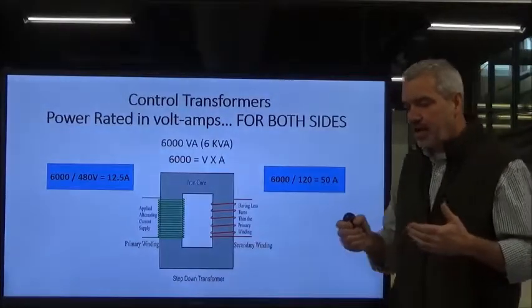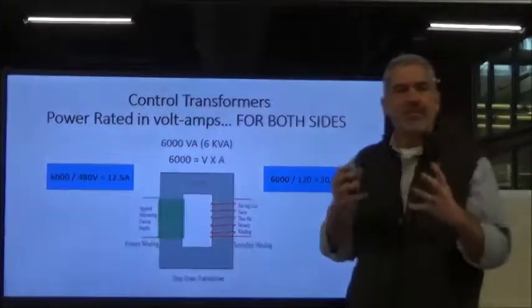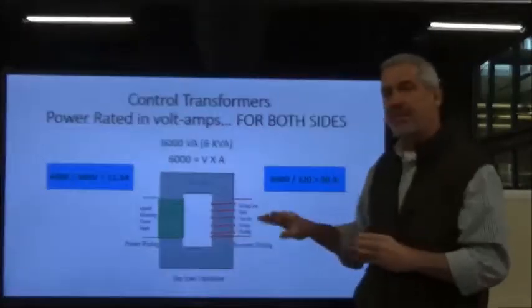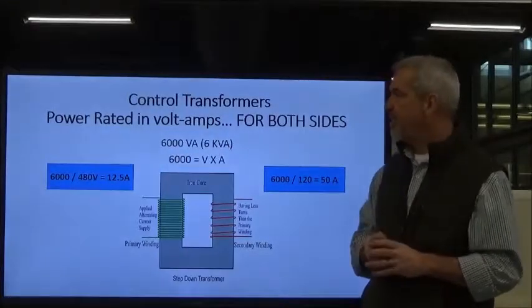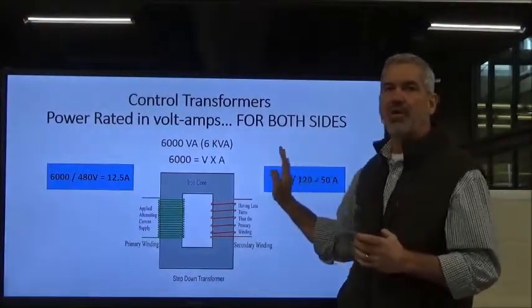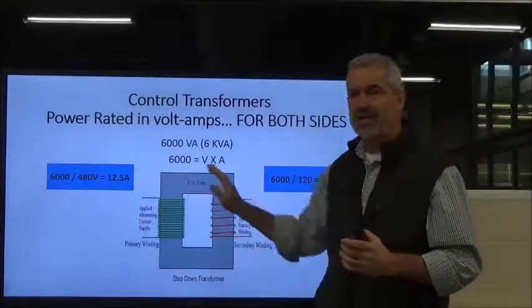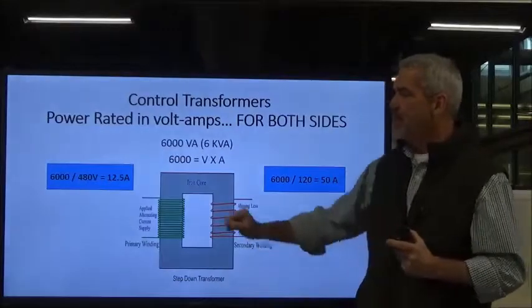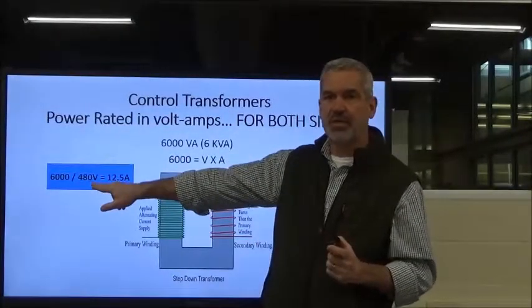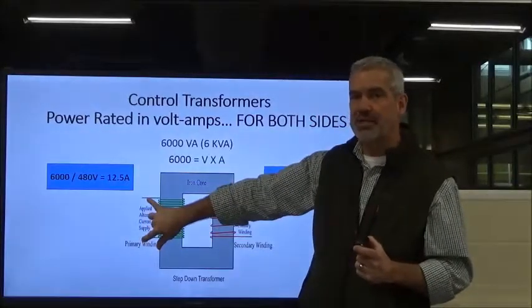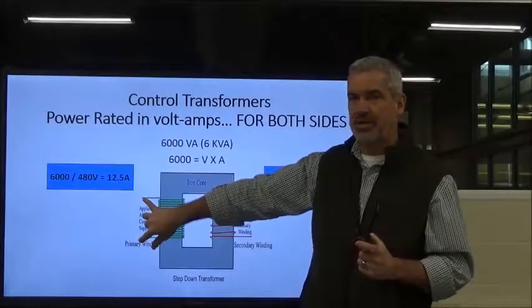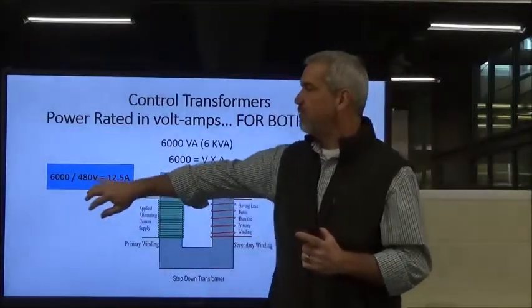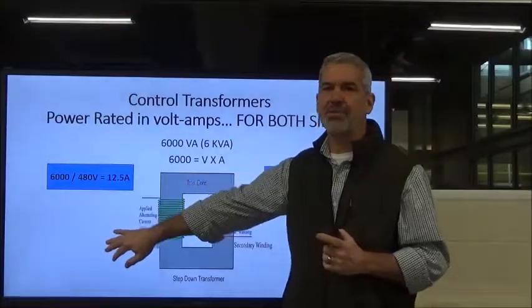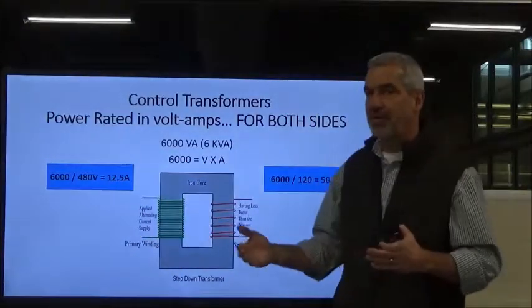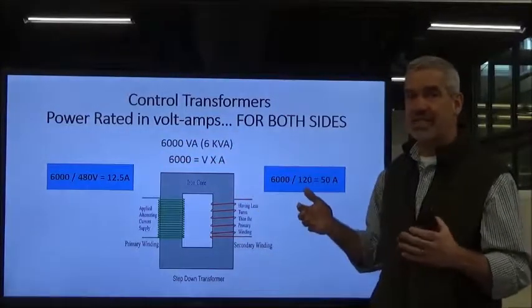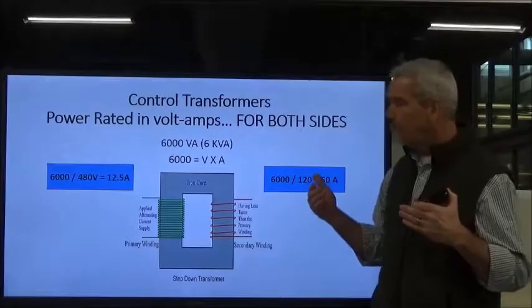And remember, we said it's a lot like that blow dryer we were looking at. 1500 watts is 1500 watts. It never changes. Same thing with a transformer. If we have a 6,000 volt amp transformer, that's 6,000 volt amps on either side, whether it's the primary or secondary. That does not get affected by the step up or the step down. So I've got a 6,000 volt amp transformer, and I'm putting 480 volts into my primary circuit right here. I can take 2 of those phases in our drawing we saw a minute ago and apply it right here. Just hook it up there, create that magnetic field. With 480 volts, I'm going to have 12.5 amps on the primary side. Remember, nothing changes with a 6,000 volt amp. It's still a 6,000 or 6 kVA transformer regardless.